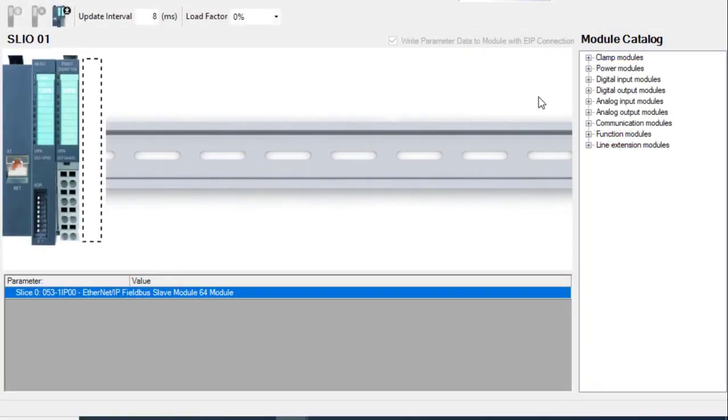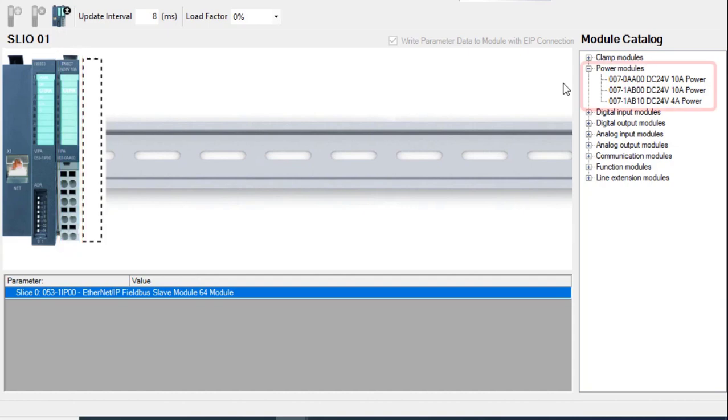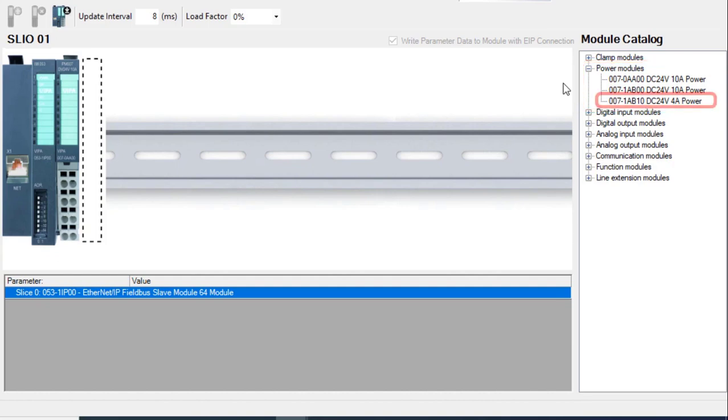To wrap up, let's look at some of the slices that are available for the SLIO system. The interface modules automatically come with one 10 amp power supply module. More power modules are available depending on the power requirements of the slices within the system. The 4 amp power slice provides an additional 2 amps of bus power, which is used to power the logic parts of each slice.